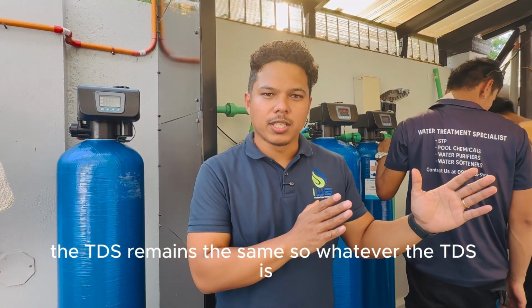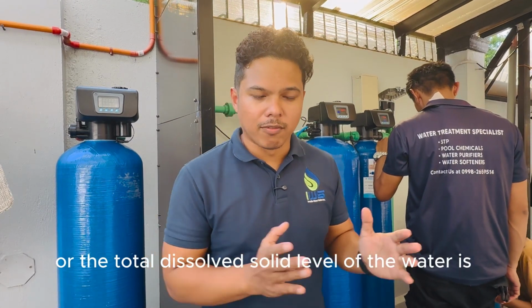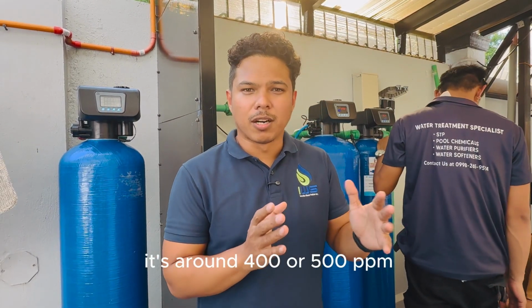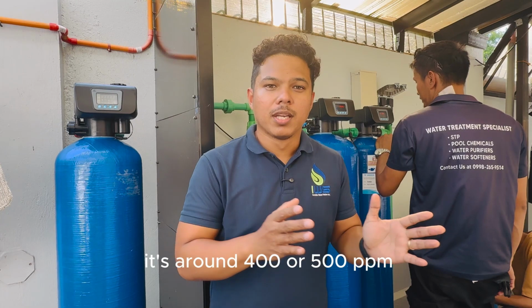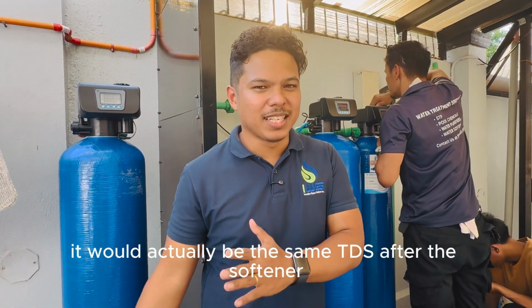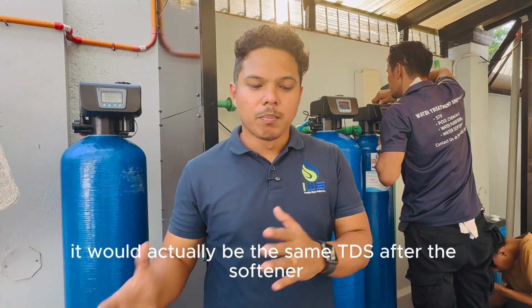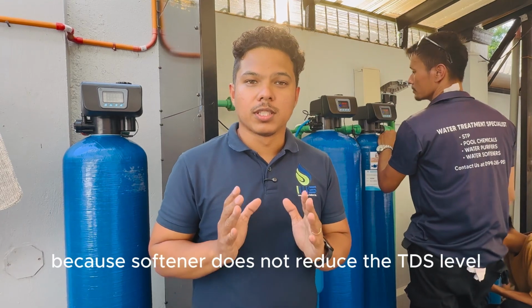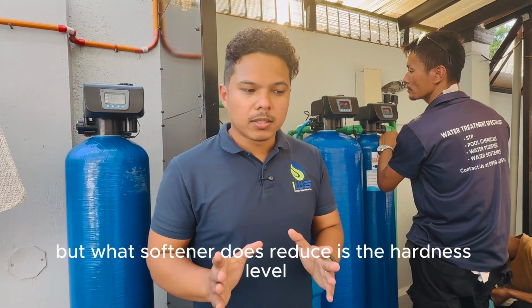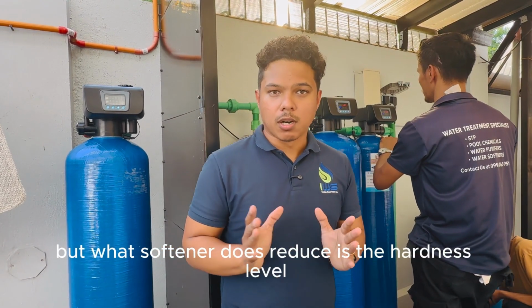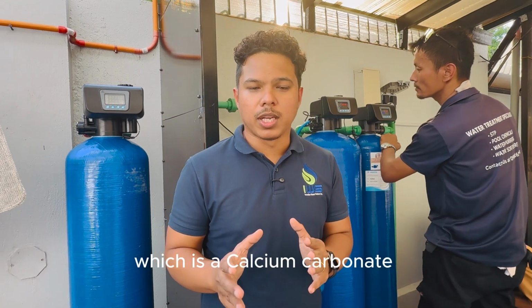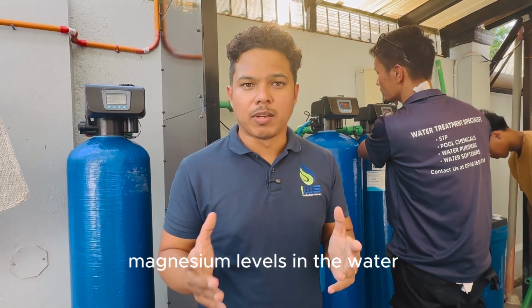Whatever the TDS, or total dissolved solids level of the water is, say it's around 400 or 500 ppm, it would be the same TDS after the softener, because a softener does not reduce the TDS level. But what a softener does reduce is the hardness level, which is the calcium carbonate and magnesium levels in the water.